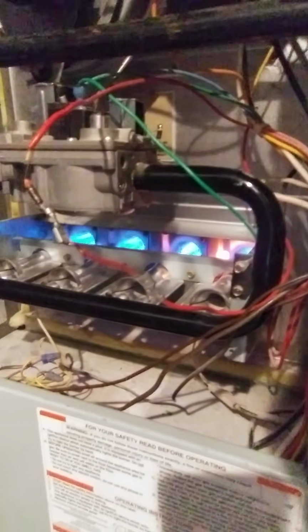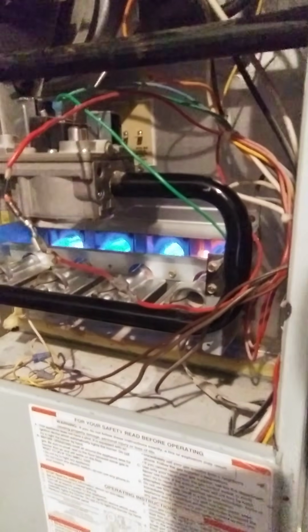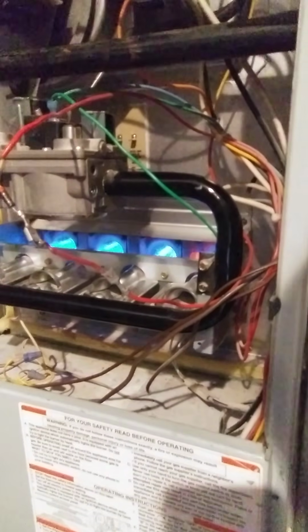Let's see if we can actually get this on video. You'll see the igniter down there starting to glow. If you don't see that glow, that's a problem—obviously the system isn't moving past this point. But since we have glow, now we have another click where the gas valve is opening, and now we have flame. So we know the igniter is good, we know the flame sensor is good, but it's hard to know those are good before you get to this point if you don't actually have those pieces working.